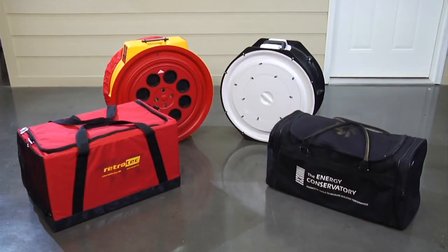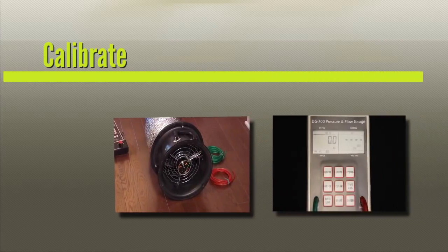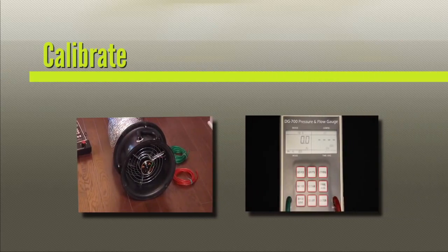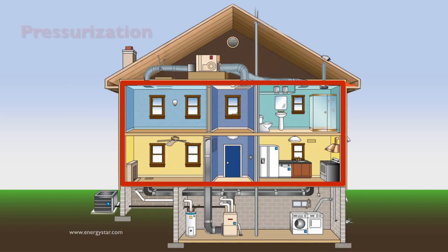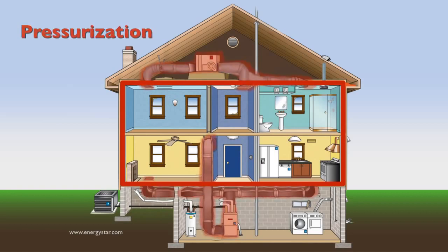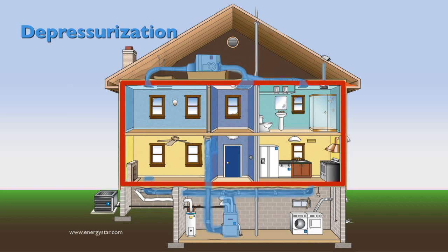There are several companies that sell duct leakage test equipment. The equipment we are using in our demonstration is from Energy Conservatory and is called a duct blaster. The duct fan and gauge are calibrated so that duct leakage is measured accurately. After the equipment is purchased, it is important it is properly maintained so that it remains calibrated before you begin any testing. There are two types of tests you can run: a pressurization test and a depressurization test.